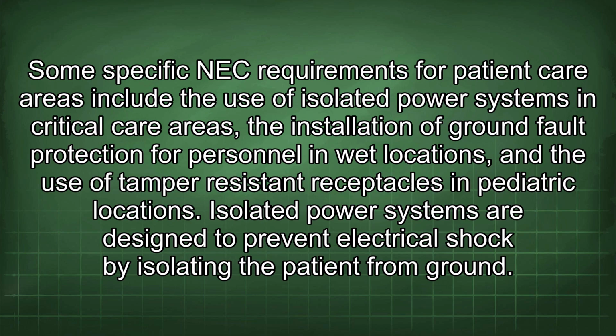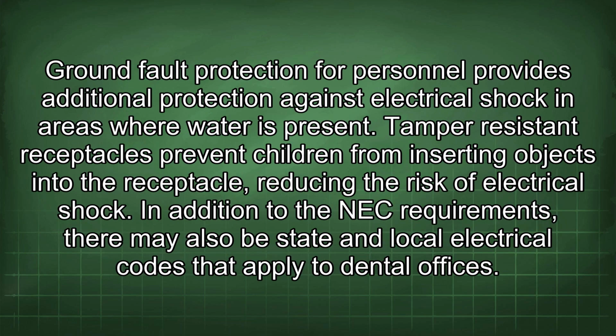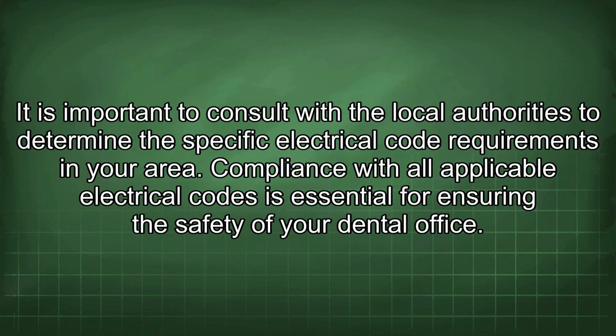Isolated power systems are designed to prevent electrical shock by isolating the patient from ground. Ground fault protection for personnel provides additional protection against electrical shock in areas where water is present. Tamper-resistant receptacles prevent children from inserting objects into the receptacle, reducing the risk of electrical shock. In addition to the NEC requirements, there may also be state and local electrical codes that apply to dental offices. It is important to consult with the local authorities to determine the specific electrical code requirements in your area. Compliance with all applicable electrical codes is essential for ensuring the safety of your dental office.